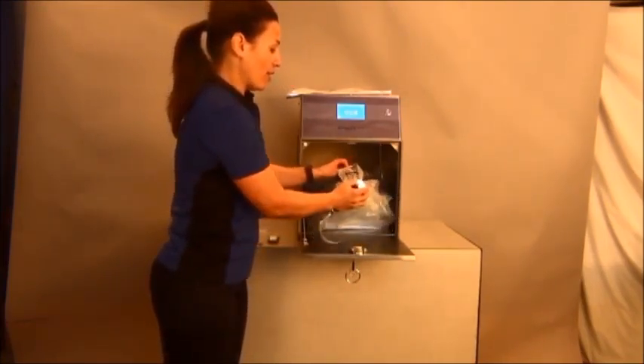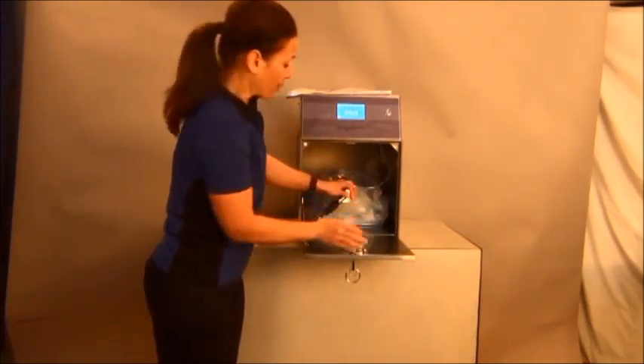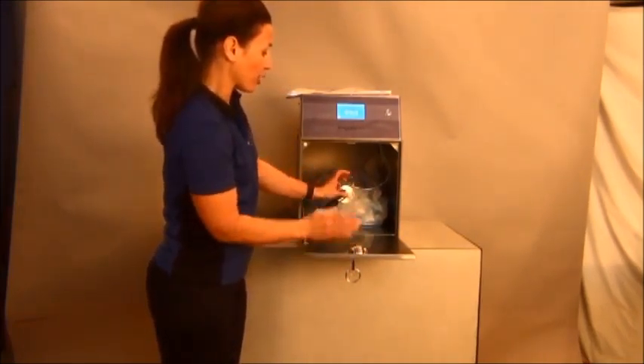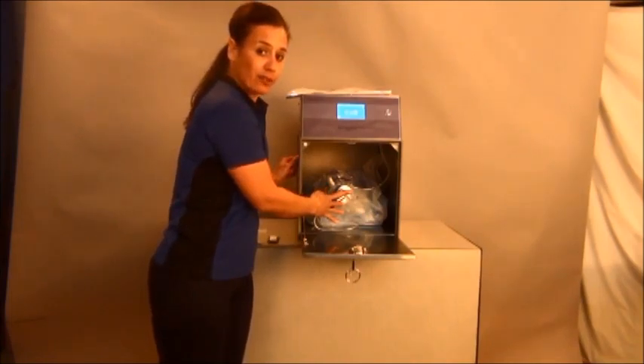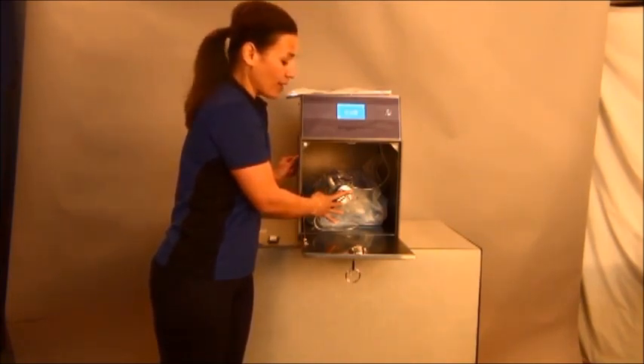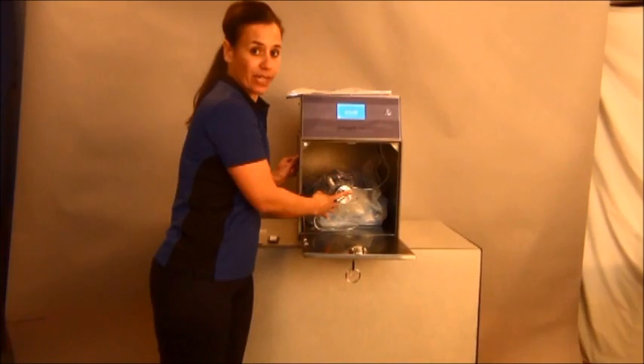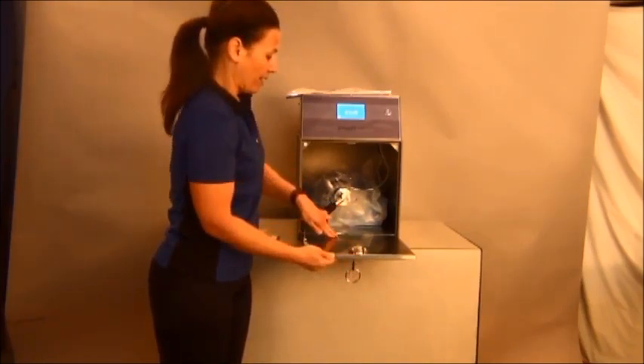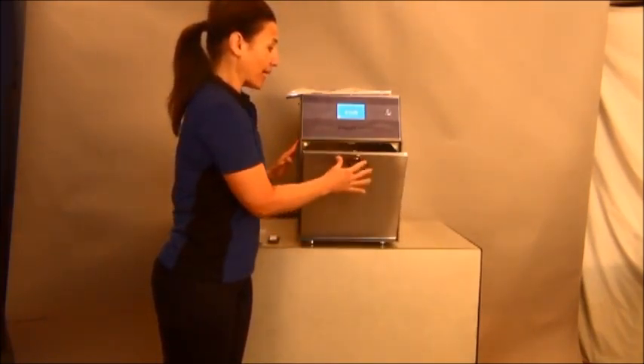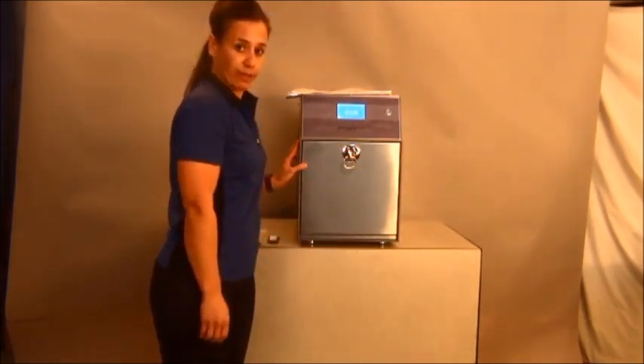At this time, push your bag into the sterilizer to make sure that the process challenge device is towards the back, so you can close the door once you activate the cartridge. If you want to verify by closing the door, you can do so at this time.